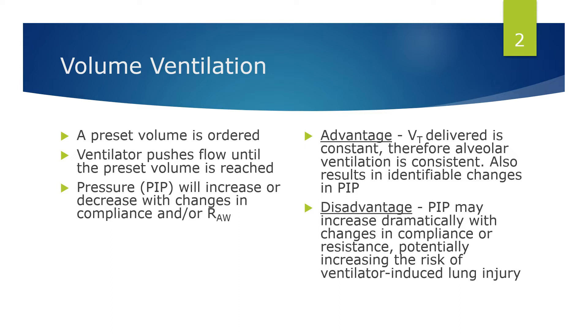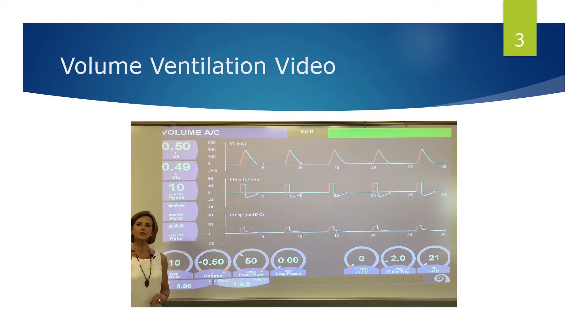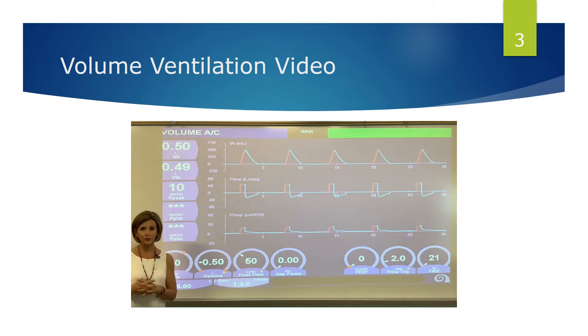The downside of this mode is that the PIP can dramatically increase when compliance decreases or airway resistance increases, and if that happens there's a higher likelihood of ventilator-induced lung injury. We are filming a two-video series to show the difference between volume ventilation and pressure ventilation, starting with volume ventilation first.